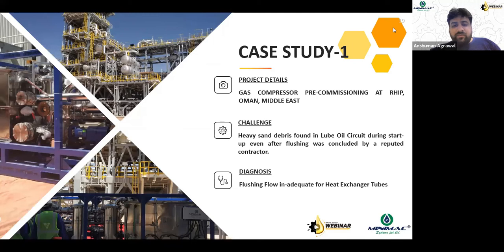So the diagnosis was that the flushing flow rate was inadequate for the heat exchanger tubes. Now, no one actually took care of the heat exchanger because of the very reason that the heat exchanger was already factory flushed by one of the reputed heat exchanger manufacturers. So no one took care about the heat exchanger.